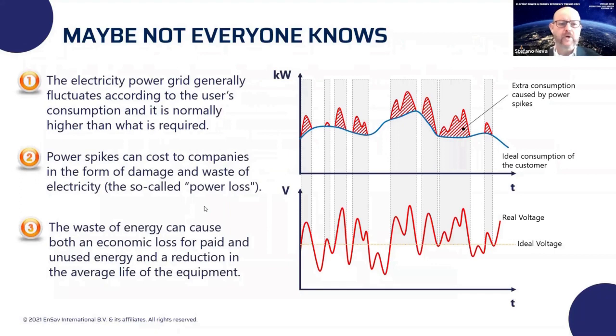So why do we say that voltage optimization is so important? You may know that voltage supply is not stable by nature and can be influenced by several factors, such as the distance between the source of energy and the consumption point, the number of users attached to a specific line, the length of the cable, the dimension of the cable, and the age of the cable. So there are a lot of factors that will influence voltage stability.